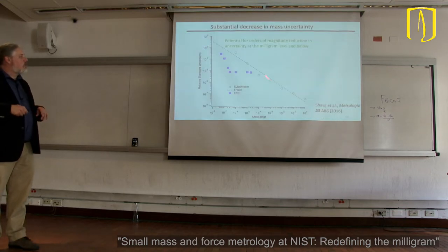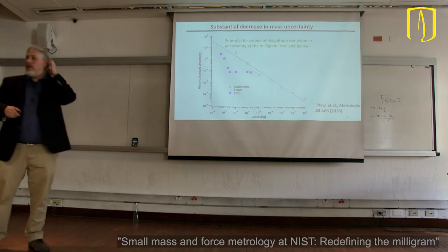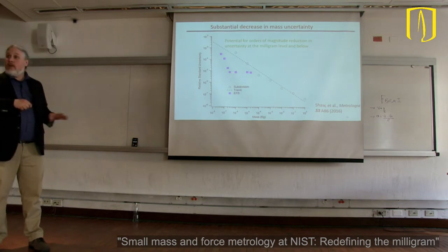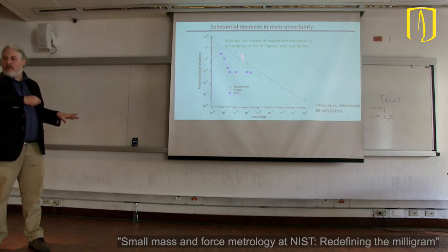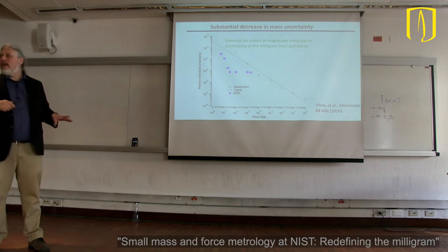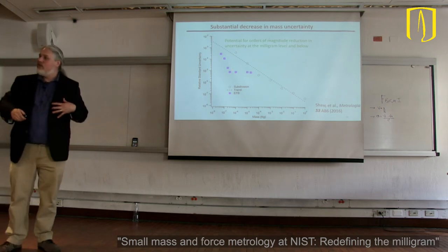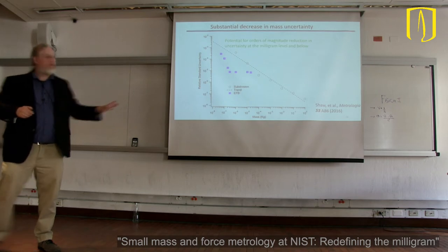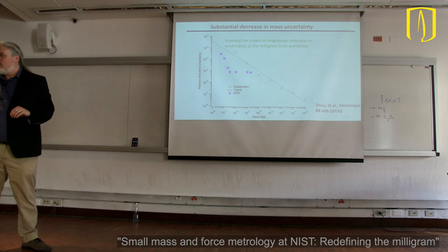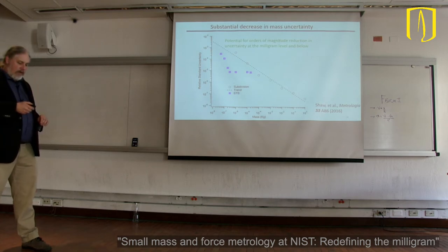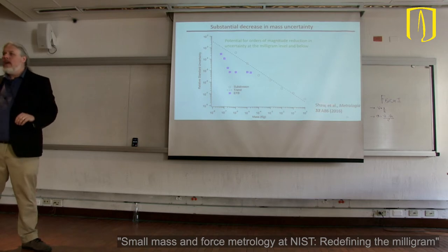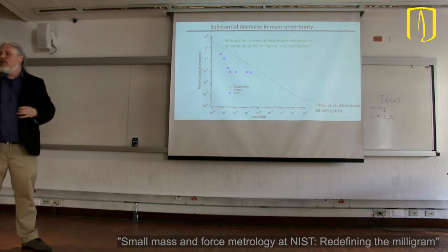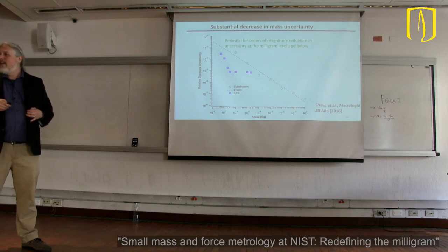Okay? So here's where we were in subdivision with the kilogram. And once again, this is the mass level, and this is the uncertainty of the mass. And you can see, here's where the EFB is active, and we're reducing uncertainty by two orders of magnitude at certain points. And remember that transition I mentioned, where we go from systematic to statistical uncertainty? That's where it is. This is my balance resolution. This is where you can see that my balance has limitations too. There's only so far I can go with this balance. But it's certainly an improvement over the subdivision method, at least for now. Okay? If you're really interested in this, I have a paper out in Metrologia that goes through much more detail than I have here. So if you are really interested in being a measurement geek, you can go look this up.